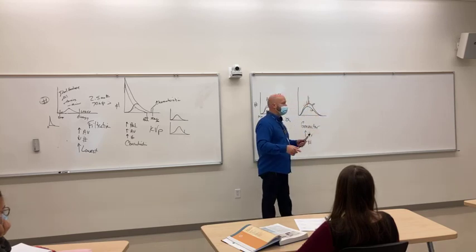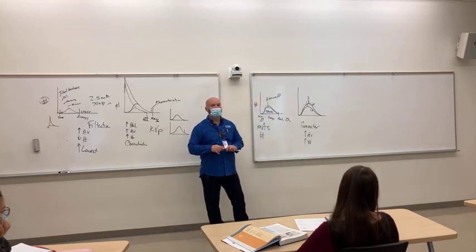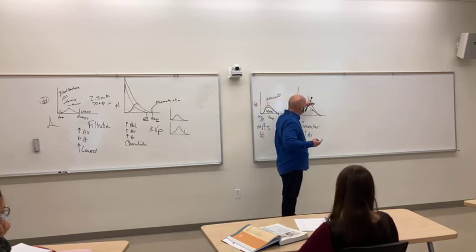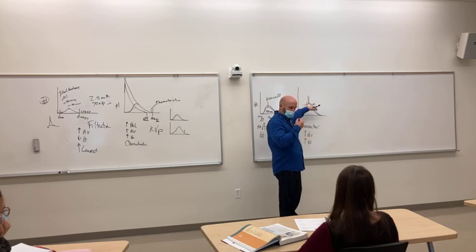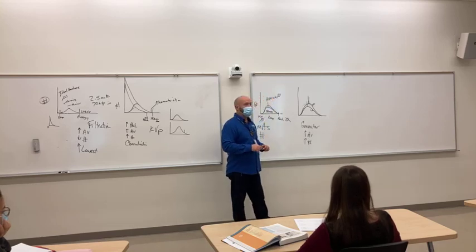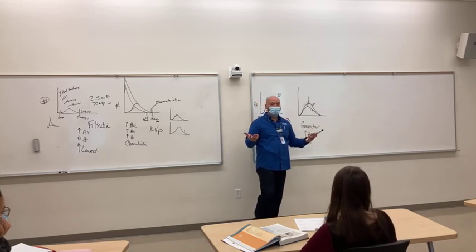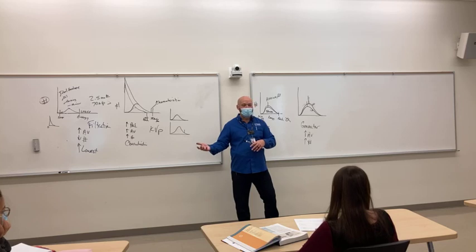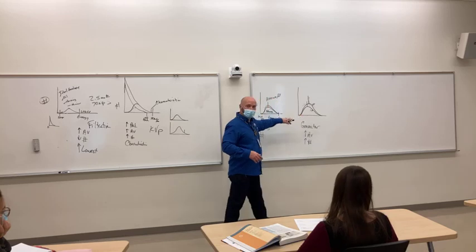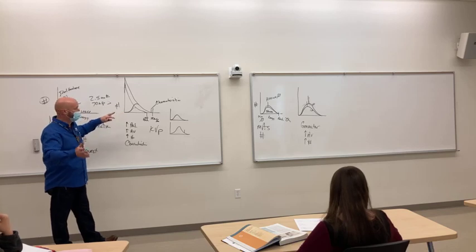What is your technique compensation or your technique change for three-phase to single phase? Factor of 2, right? So you went from a three-phase that had this output and that average to a single phase which had that output and that average. What's your new technique? You have to multiply it by 2, which tells me you didn't hear my technique to begin with. 30. So now your new mAs is 60. Okay?